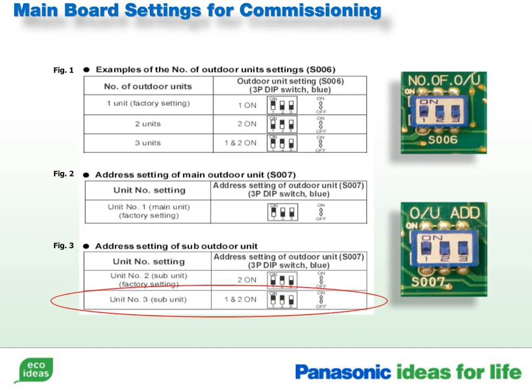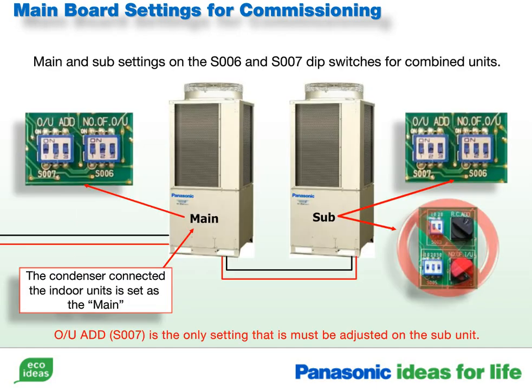The third condenser will be configured as outdoor unit number 3. This is done by placing dip switches 1 and 2 to the on position. The third dip switch is set to off. In this example, the condenser on the left has been set as the main unit, because the control wiring is connected to the first indoor unit in the daisy chain.